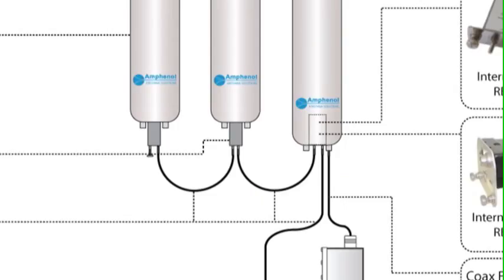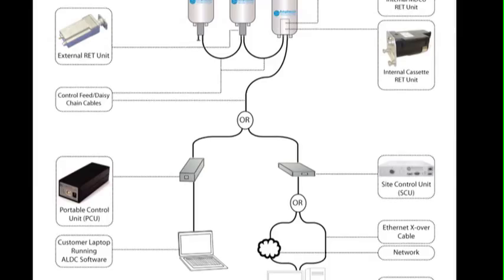Communication between antennas can be accomplished by using a daisy chain installation by using a standard AISG cable with 9-pin circular connector. Communication from the AISG controller to the antenna system can be achieved by a home run cable, which is a long AISG cable running the length of the tower, or a Smart Bias T system. Smart Bias Ts contain AISG modems which allow AISG control and DC power to be injected into the main feeder line. The bottom bias T injects the signal and DC current into the feeder line, and the top bias T removes the DC current and AISG signal from the main feeder to power and control the antenna RET units.